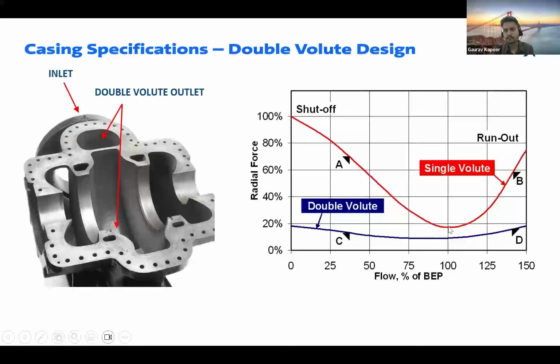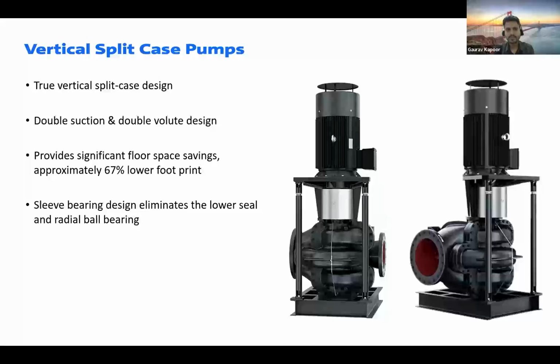Now for a single volute pump at the best efficiency point, the radial forces will be around 18 to 20%. But if you look at a double volute pump, across the operation of the flow from 0% to 150%, it's always lower than the radial forces in a single volute pump. So that's why for large size pumps which are needed in a district cooling plant, it is always recommended to use double suction and double volute pumps, so that you can have very low radial forces and axial forces, which helps you have a very long life of all the components in a centrifugal double suction double volute split case pump.